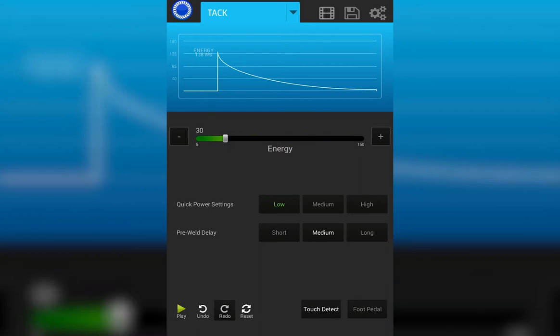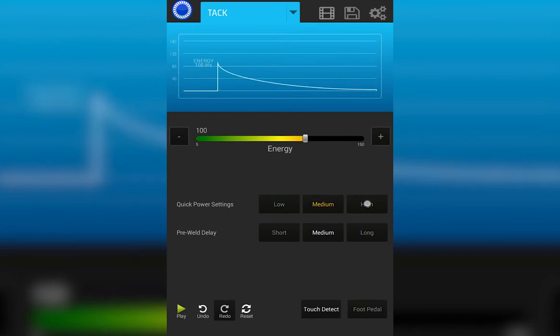Just below the energy slider bar, you see we have the quick power settings. These are a quick and easy way to adjust the weld energy. From a low setting with 30 joules of energy to 100 to 150.